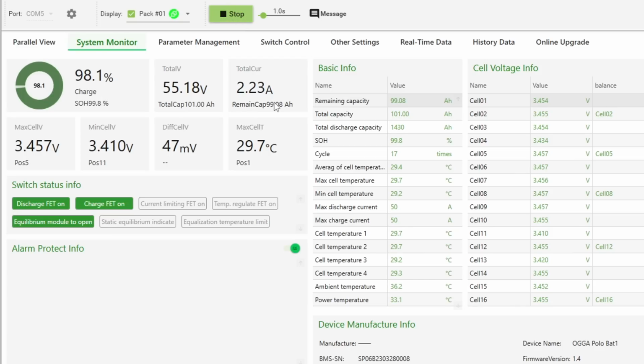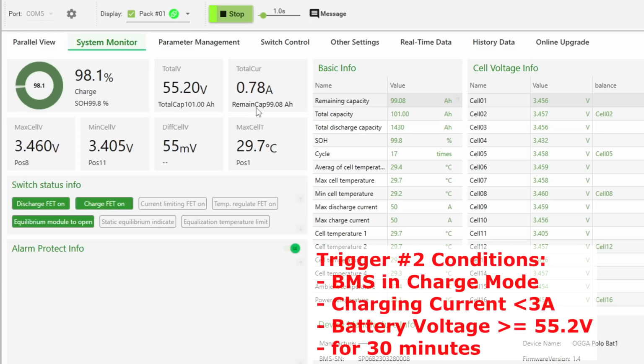You can see the current is tapering off. We've got full sun outside, but the current is going down - look, 0.7 amps after 2 minutes, 3 minutes. We're almost at 0.5 amps, which is the threshold for this BMS, I believe. So if it goes to 0 we'll see standby here, and the timer resets to 30 minutes again. It will never charge for half an hour in these conditions.